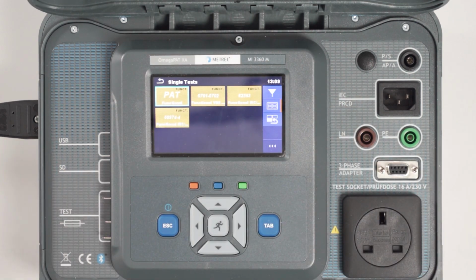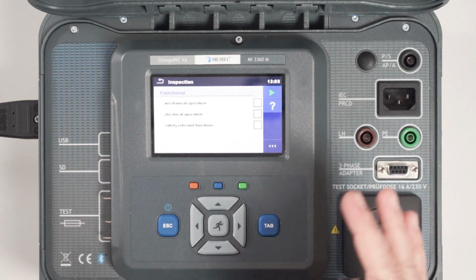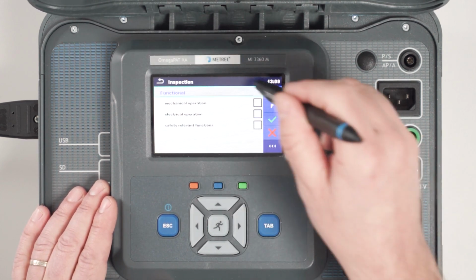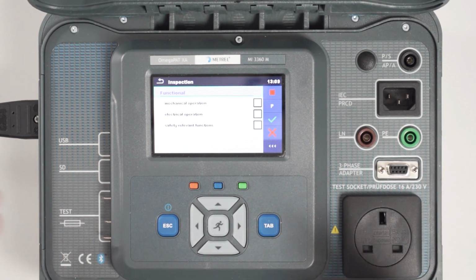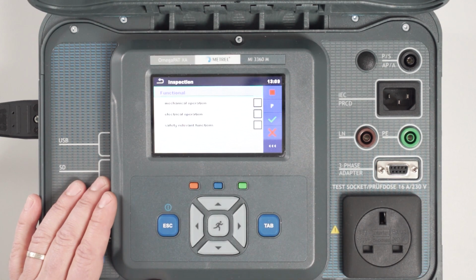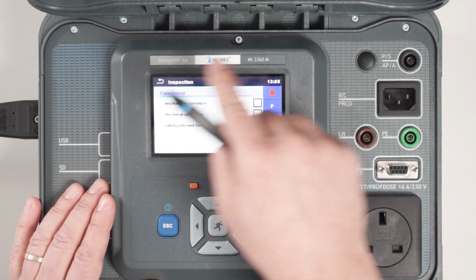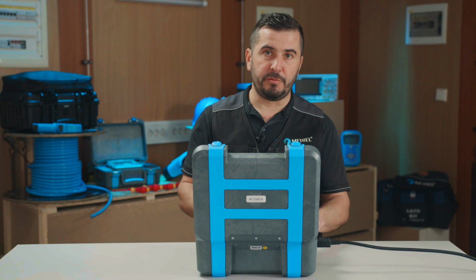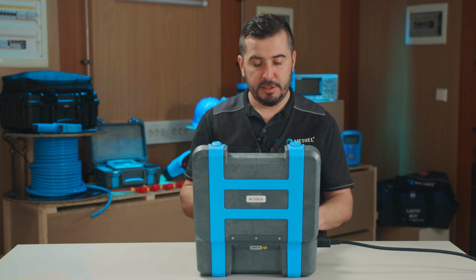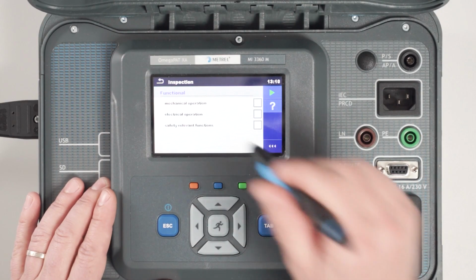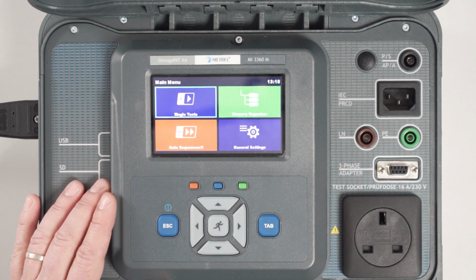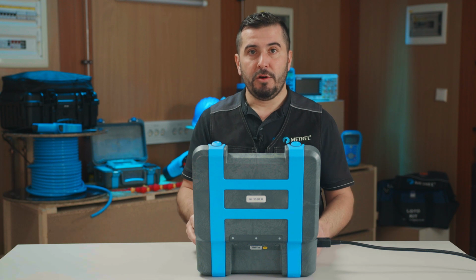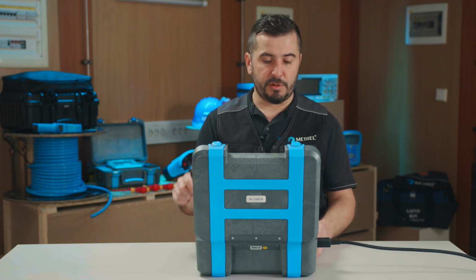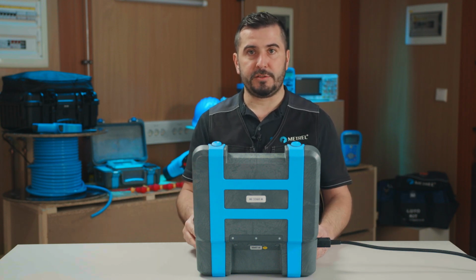And the last one here is the menu from where we can select functional inspection. These functional inspections that are predefined from Metrel have the possibility to add criteria, so mechanical operation, etc. We can also add some additional parameters here, but what is important is that during this functional inspection we can also measure the power and confirm whether the power of the appliance meets the inspection criteria. I will stop this and return back to the main menu. This is practically all about the single test menu, and also about the main menu of our test instrument.